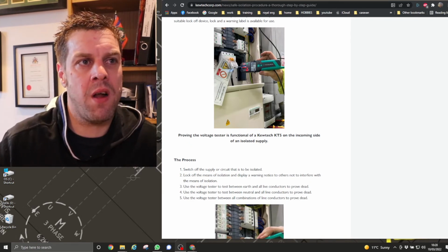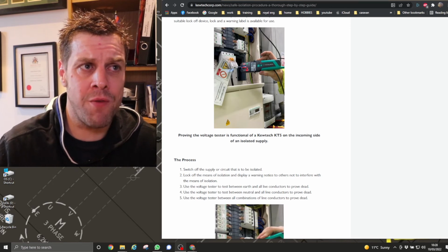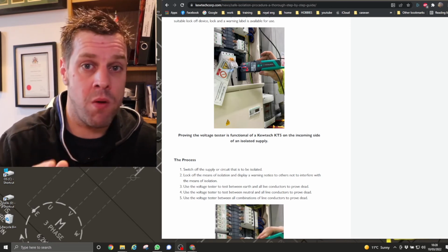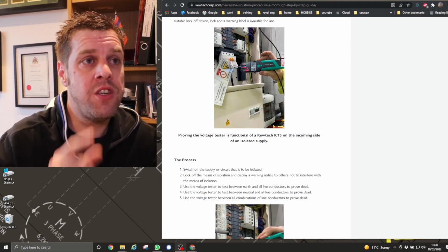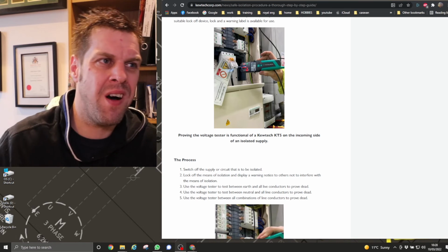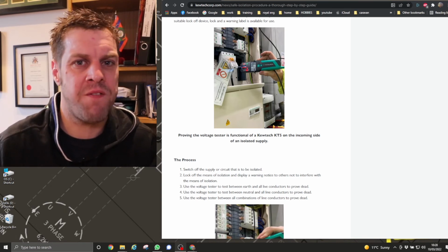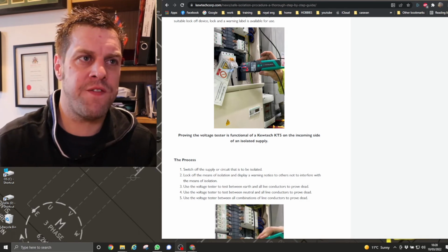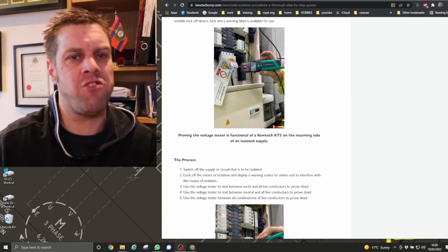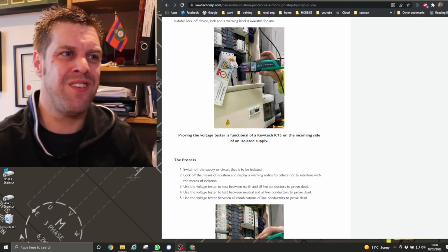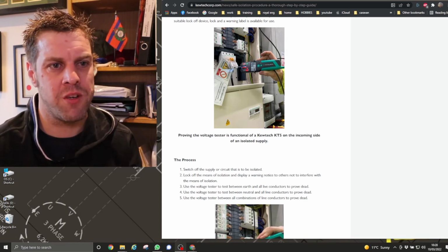And we all know when it comes to PR like this, it's put out from your department using your tester. These are staged photos. You've staged these photos, as someone pointed out when I put this poster on Twitter. No PPE on. Yeah, right, you're not that close. But flashover, arc flash is a killer. And also, you could have staged these photos loads easier by showing where you locked it off at the other end and doing the test on one of your own proving units, not on a known live supply that's in the same enclosure you're going to work in.